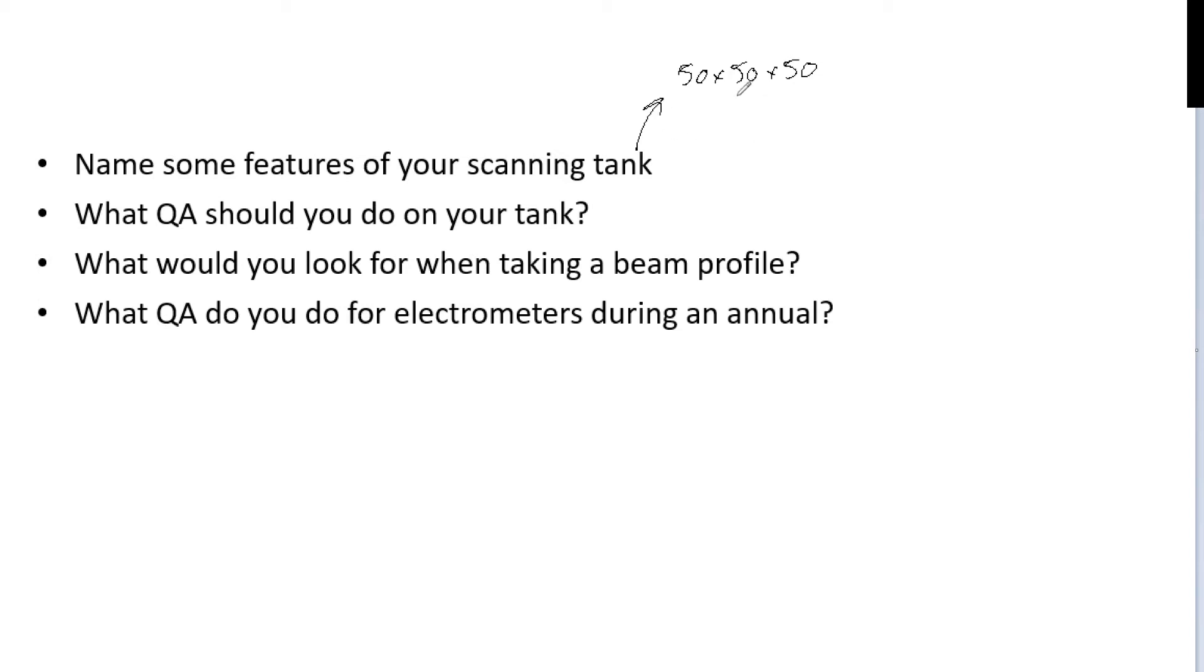Now, it's also important that not only do you know the hardware and how big it is and those characteristics, but how you can use it. Obviously, your scanning tank, you're going to be using it for QA. This means percent depth doses, beam profiles, and TG51. Also, maybe know why you do that. Why don't you want to use just solid water or something of that nature?